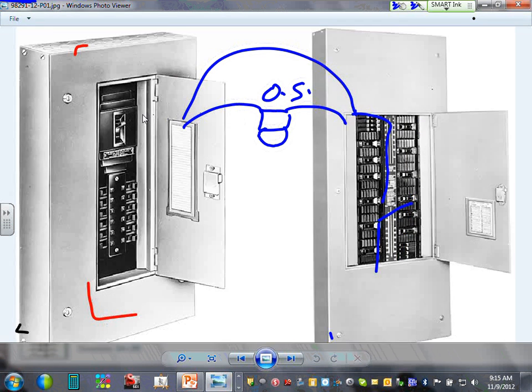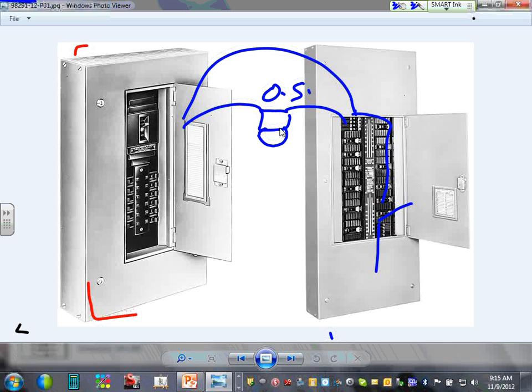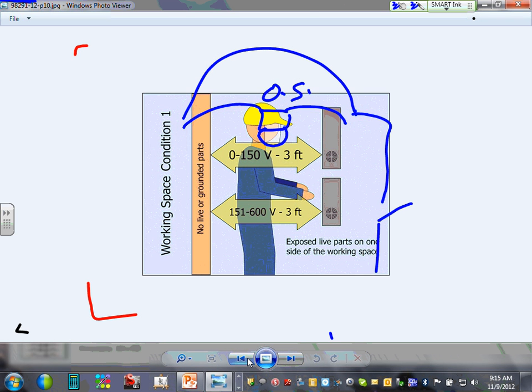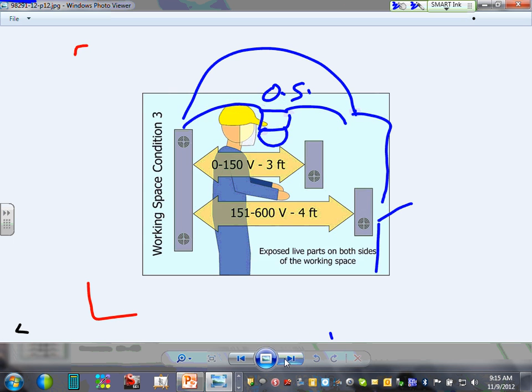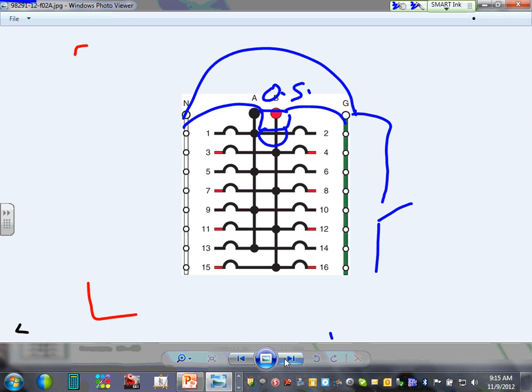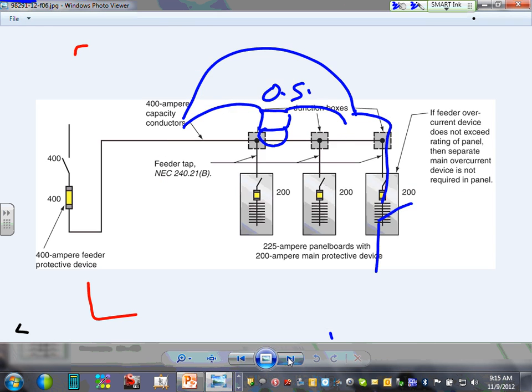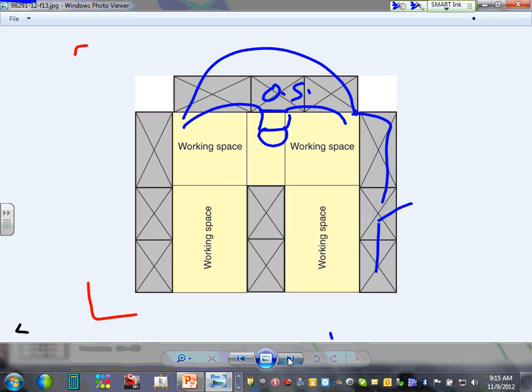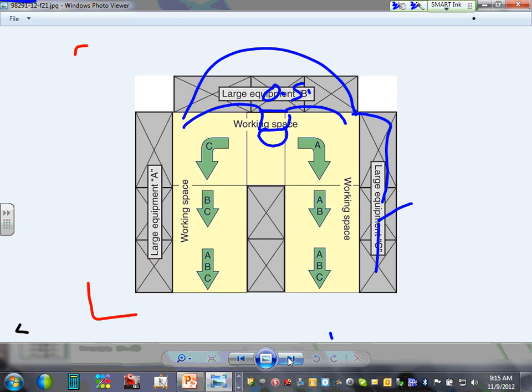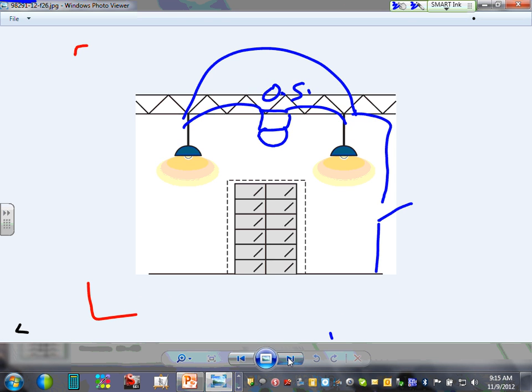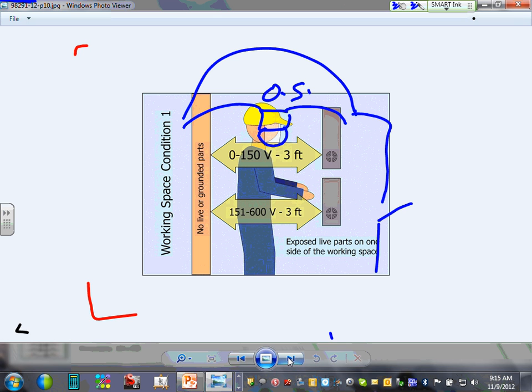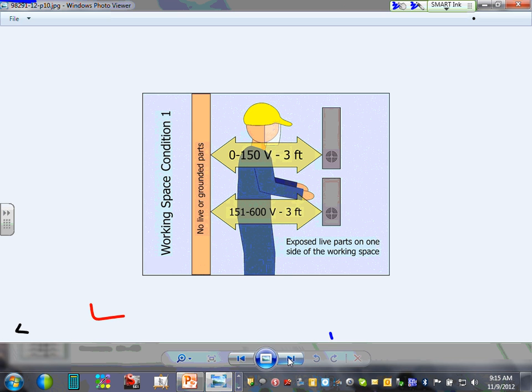Okay, here's how your panels look, guys. You're looking at main circuit breaker here, main lugs only. We talked about the clearances. You guys remember the clearances in front of the equipment. So that's really all I want to do about this chapter. Let me just summarize and let you guys go. I don't want to go even to my PowerPoint presentation because really the PowerPoint is right here. Summarize. When you have a panel, they arrange the phases left to right, A, B, C. The neutral will be on the left, the ground will be on the right.